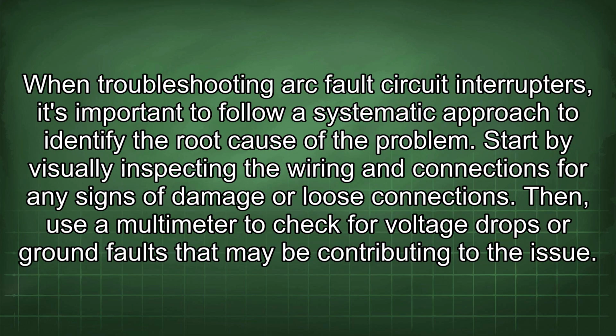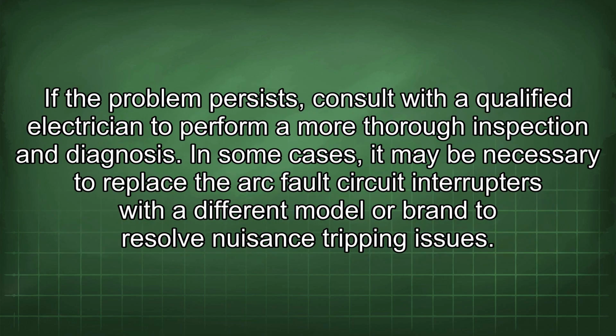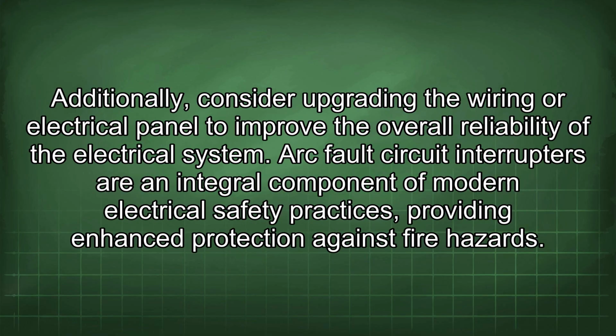When troubleshooting arc fault circuit interrupters, it's important to follow a systematic approach to identify the root cause of the problem. Start by visually inspecting the wiring and connections for any signs of damage or loose connections. Then, use a multimeter to check for voltage drops or ground faults that may be contributing to the issue. If the problem persists, consult with a qualified electrician to perform a more thorough inspection and diagnosis. In some cases, it may be necessary to replace the arc fault circuit interrupters with a different model or brand to resolve nuisance tripping issues. Additionally, consider upgrading the wiring or electrical panel to improve the overall reliability of the electrical system.